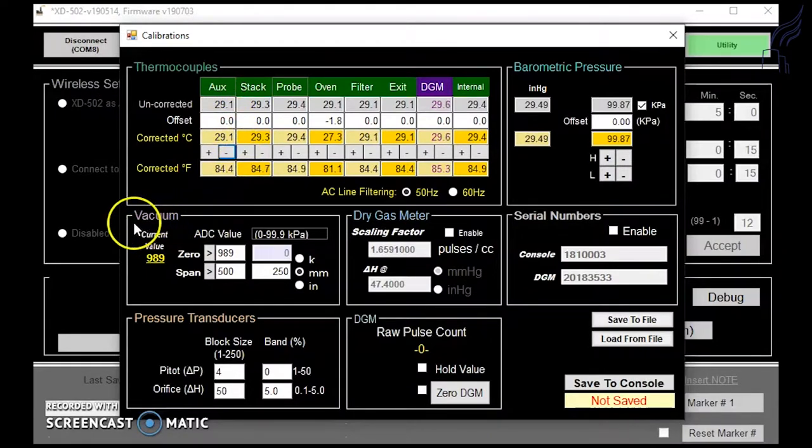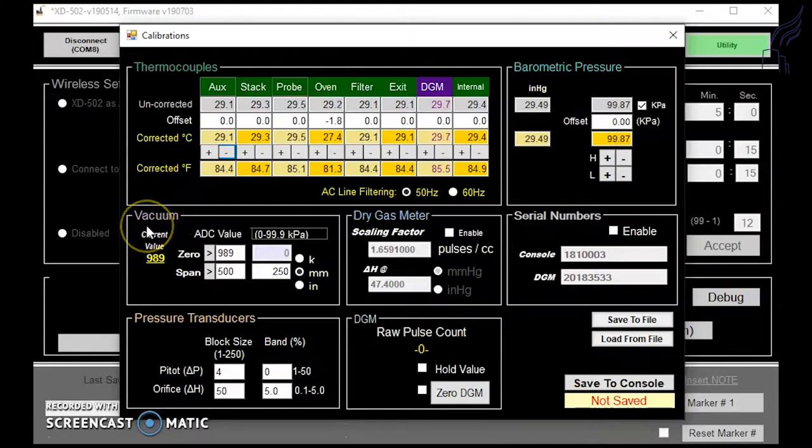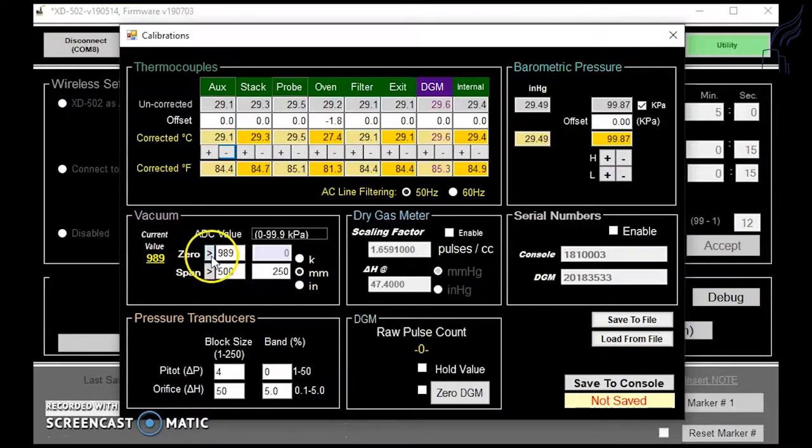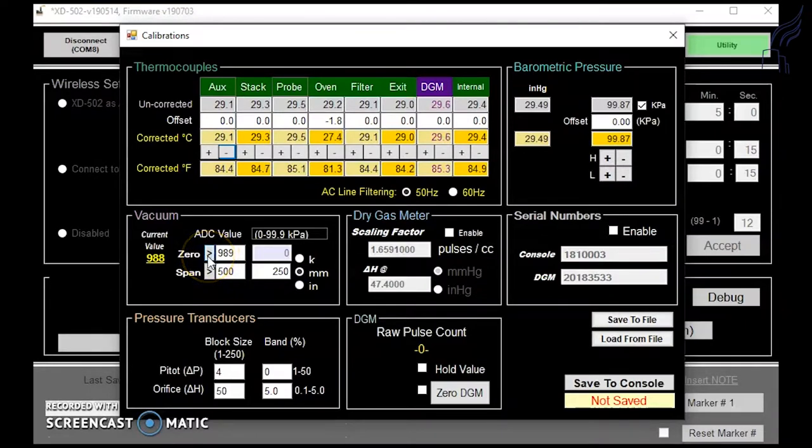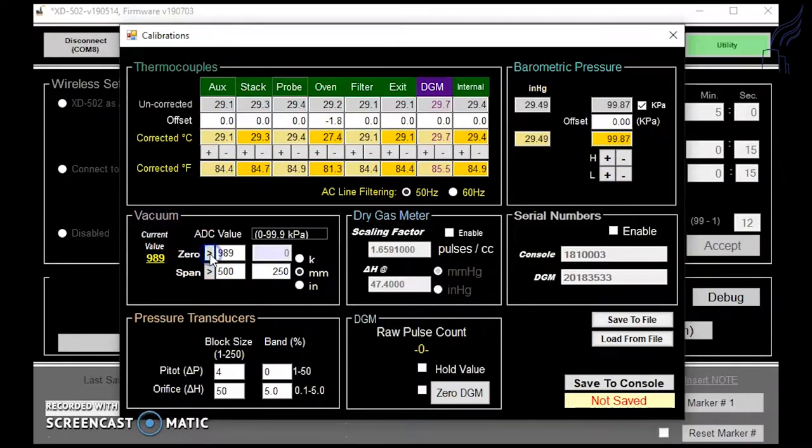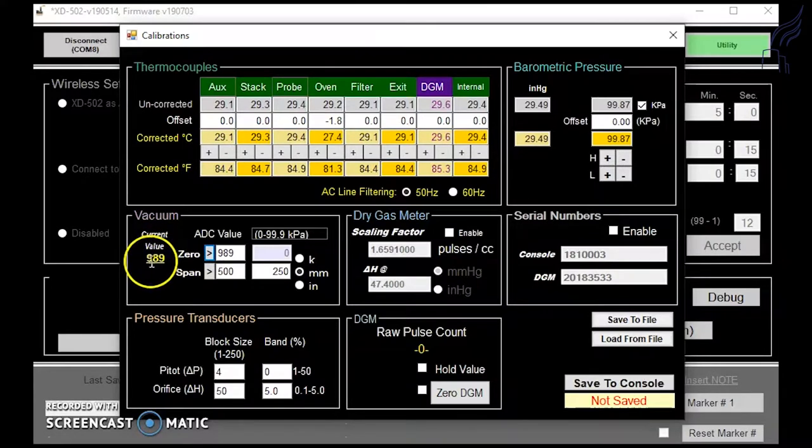You can also use a reference vacuum gauge to calibrate your vacuum. With nothing inserted into your sample inlet, you can click on the arrow here and get your zero reading. It captures the current value displayed here for zero.